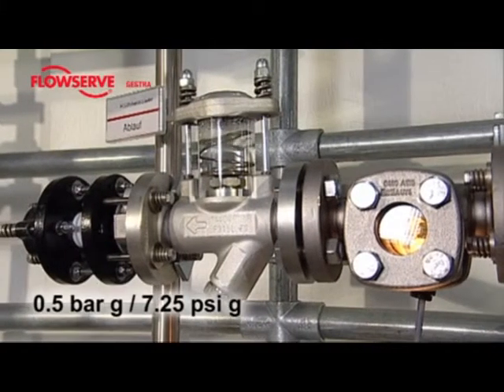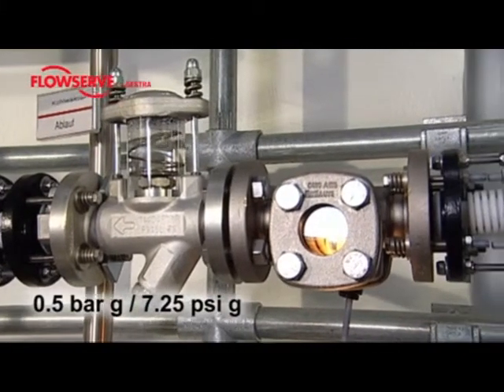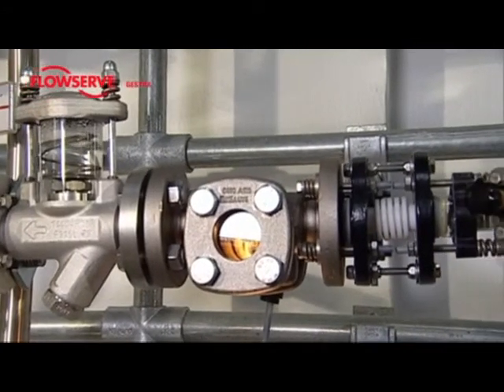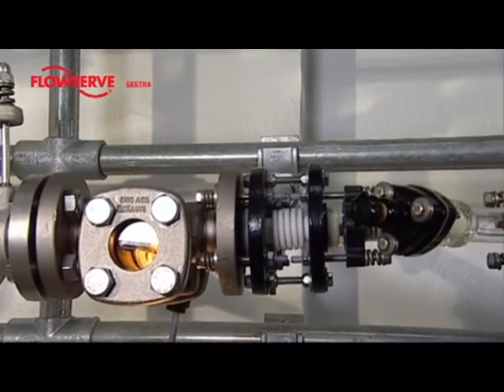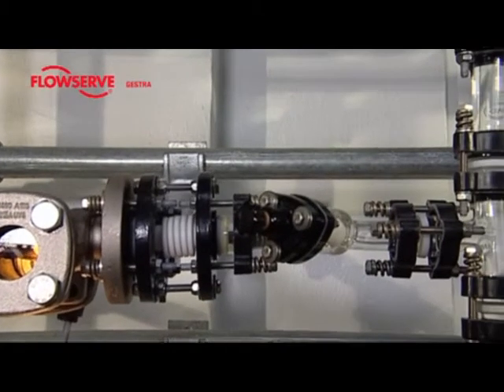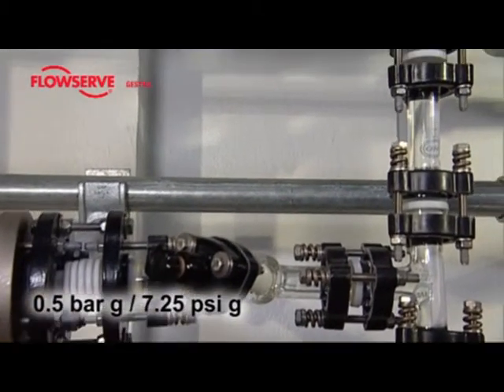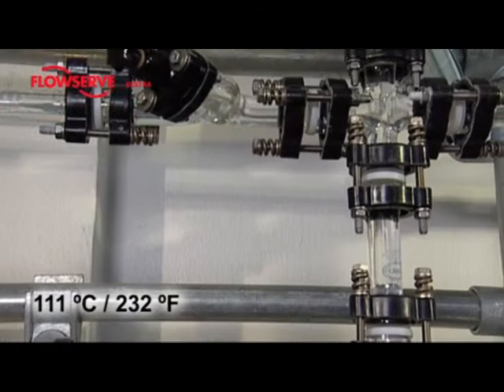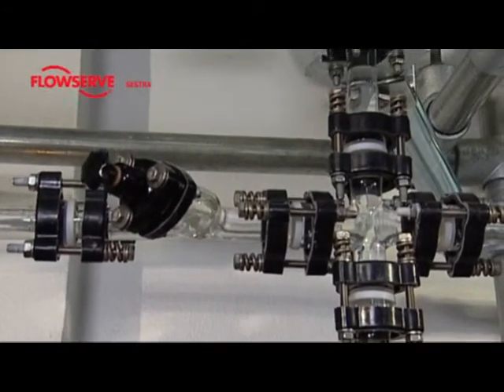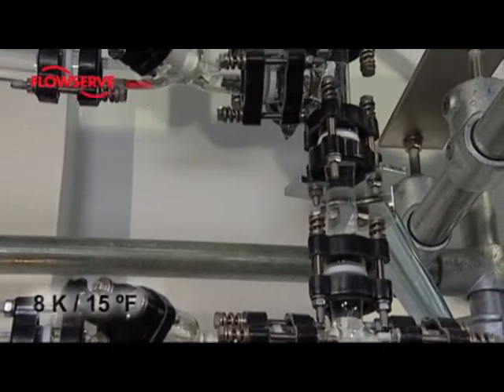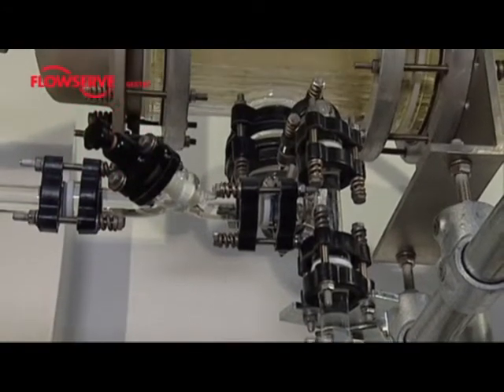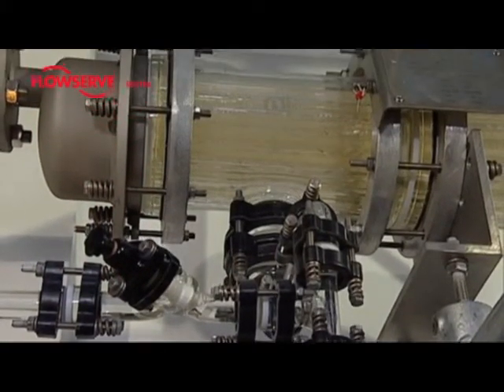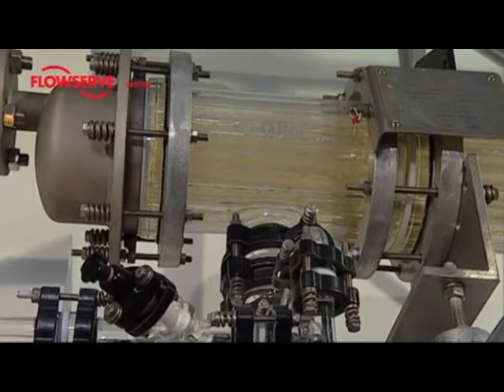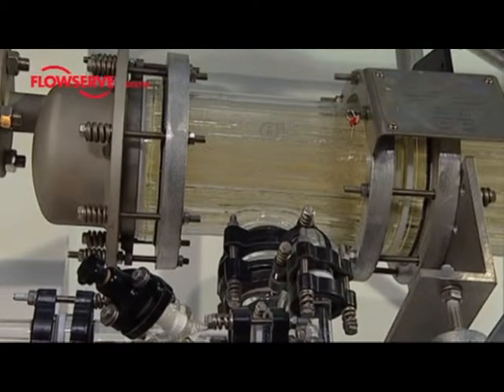The operating pressure is reduced to 0.5 bar G. Owing to the reduced boiling point, the steam trap closes initially. Once the pressure and temperature have settled down to the values 0.5 bar G and 111 degrees centigrade, the membrane steam trap opens as soon as the undercooling reaches 8 Kelvin. Because of the lower pressure difference, it's no longer possible to discharge the entire quantity of condensate.